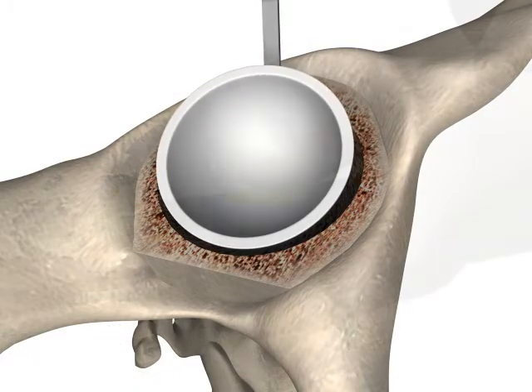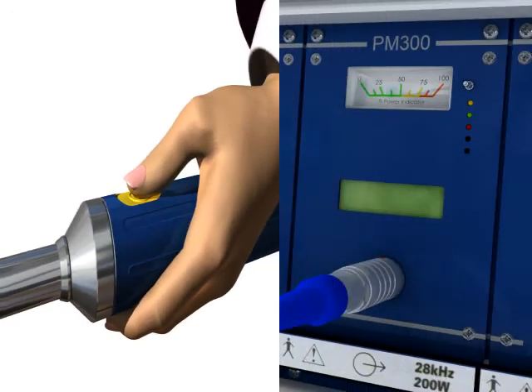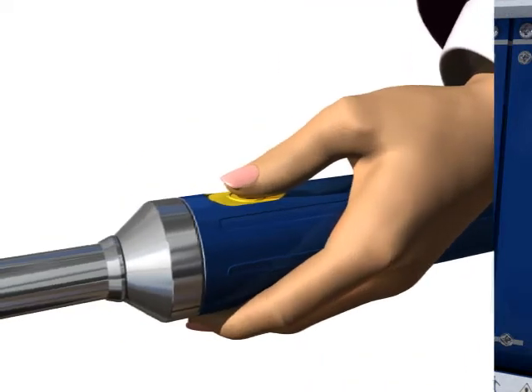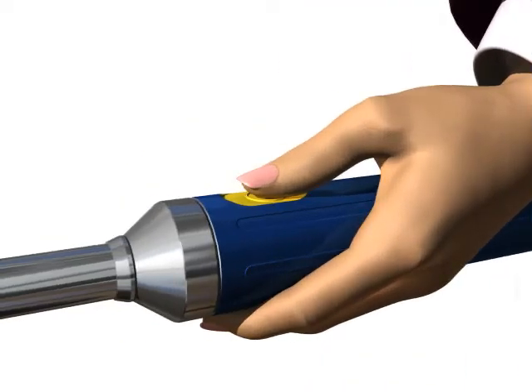It is important to remember to activate the probe before advancing into a previously created slot and to not create manual pressure before activating the probe. Doing so may lead to the probe improperly tuning and possibly breaking during use.